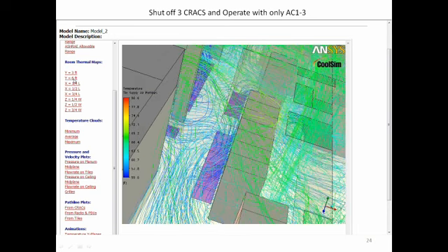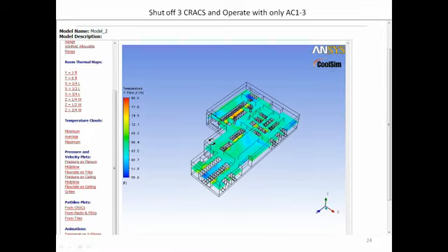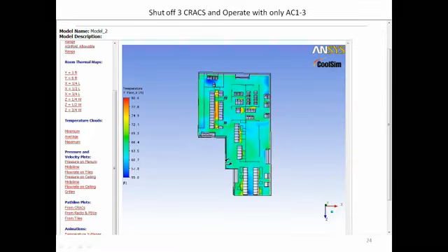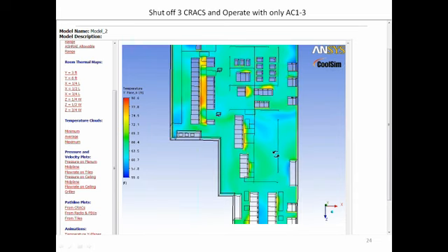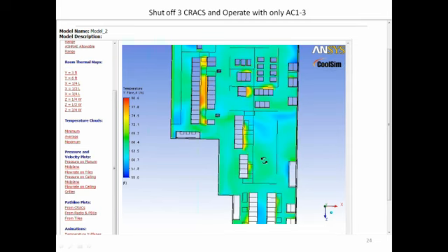So if you look at your cut planes here now at 6 feet, a lot of people like to stare at these. This is another representation. You can see here that it's in much better shape than it was before with respect to temperature. Yep, it's hot in the hot areas. It's cooler out.